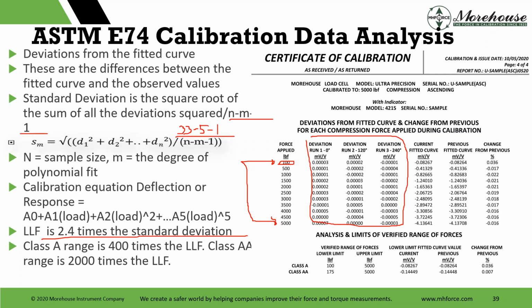convert it. The Class A range is 400 times the LLF. The Class AA range is 2,000 times the LLF, as seen right here. And here's some more things we're looking at change from previous. But look, Class A, 100. Class AA, 175, because we're multiplying by 2,000.